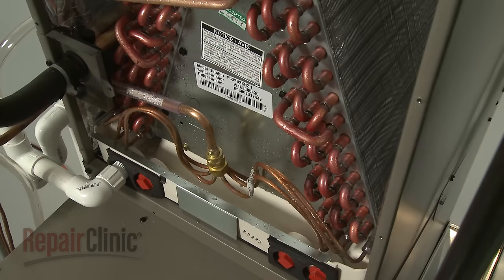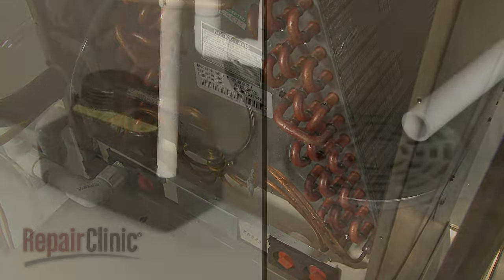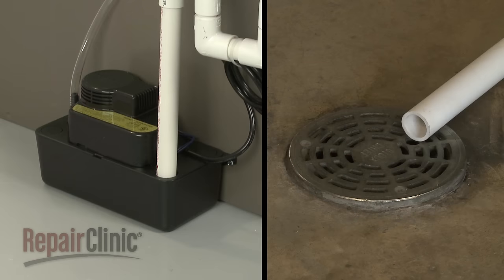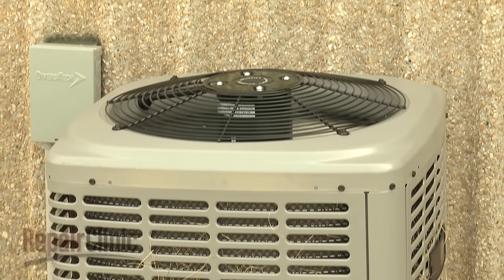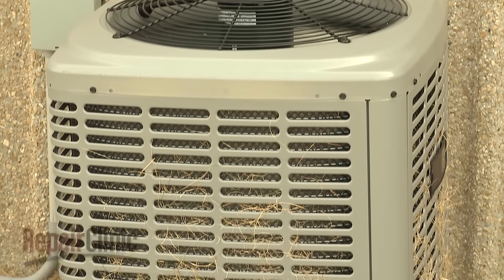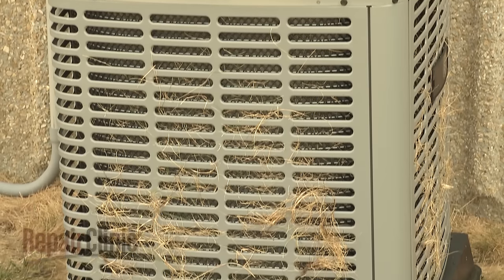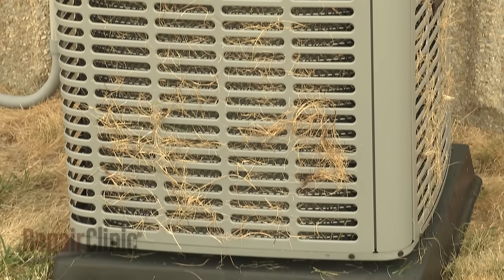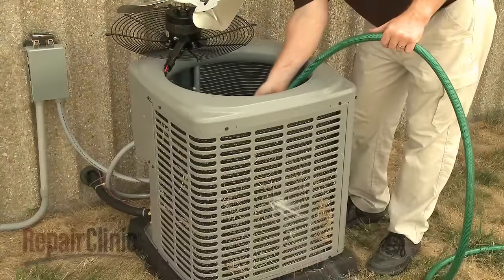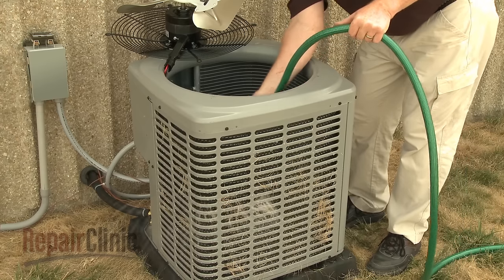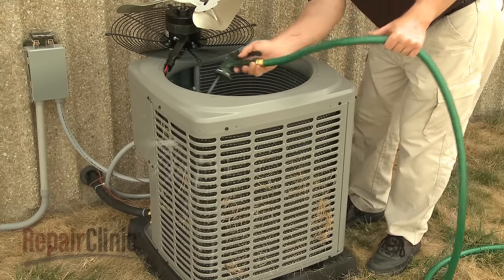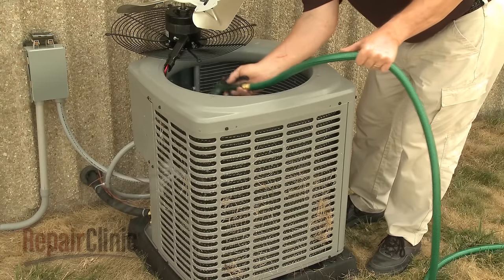The humidity in the air condenses on the cold evaporator coils and drips down into a set of collection trays. The trays are attached to either a condensate pump or a floor drain. It's important to keep the condenser clean. If leaves or other debris clog the coils, the heat will not be dissipated properly, and the system will not function efficiently. You can use a garden hose to clean the condenser by spraying the coils from the inside out.